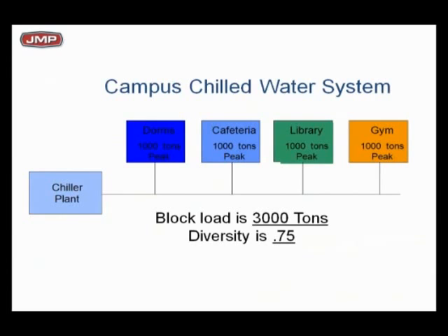So in this case, if you total up the peak loads, let me try to make an example here. You see you've got 1,000 tons each block. So your total peak load is 4,000 tons. But if you run a block load, knowing the kids can only be at one place at one time, then the block load is 3,000 tons while individual peak loads total 4,000. So the definition of diversity is 0.75. My message to you is, if we design this thing properly, we can buy 3,000 tons worth of chillers for the chiller plant. If you don't design it properly, you're going to need 4,000 tons or higher.